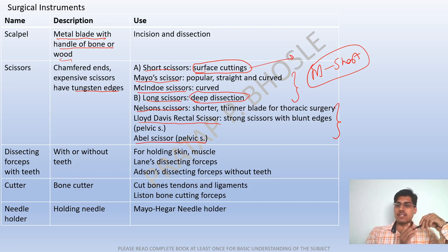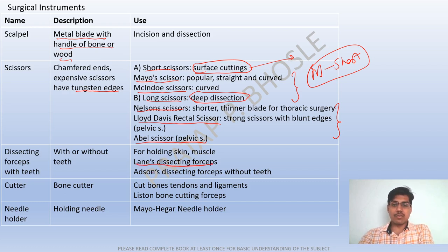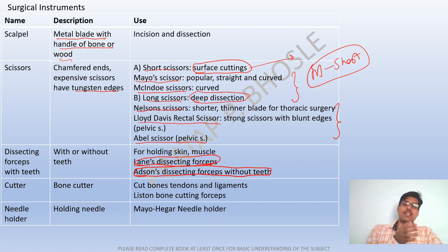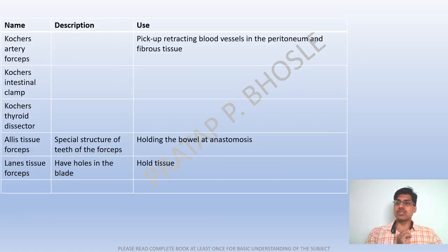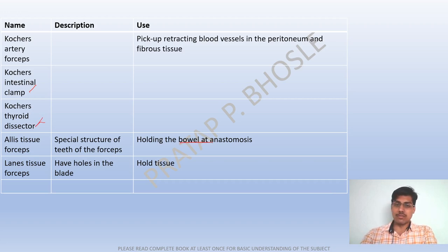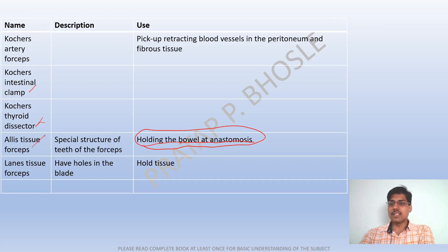Dissecting forceps are with or without teeth, used for holding skin and muscle. Lanes dissecting forceps have teeth; Adson's dissecting forceps are without teeth. Cutters are used to cut bones. The needle holder is used for holding the needle — the Mayo-Hegar needle holder is the key type. Tissue forceps, such as Lanes tissue forceps, are used to hold tissue.